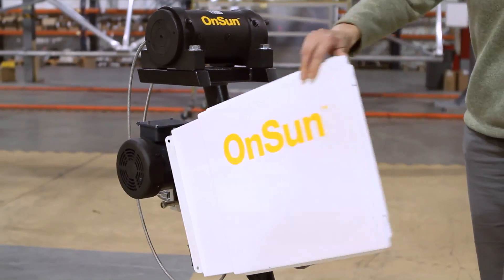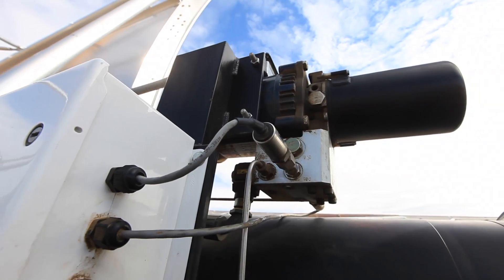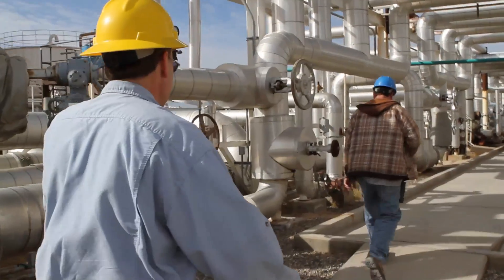Knowing the position of the SCA is critically important because we track the sun using the theoretical sun position. There are algorithms built into the SkyFuel Controller that use the date, time, latitude, longitude, and the north-south orientation of the collector.